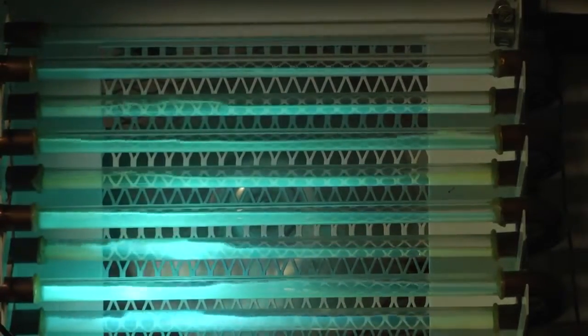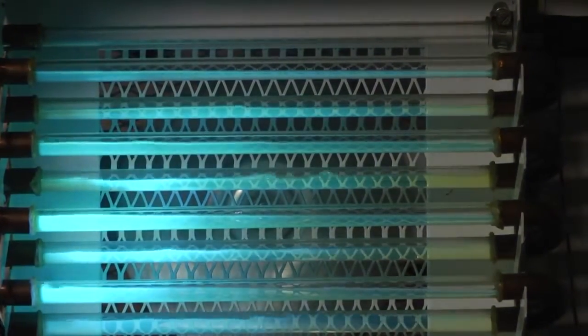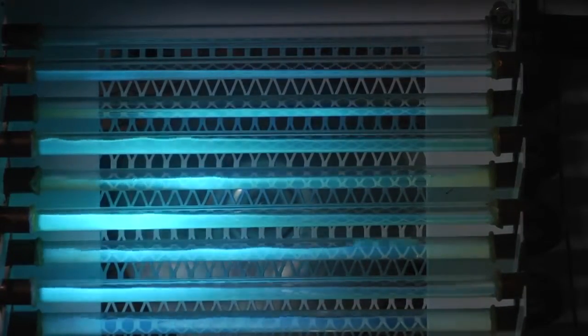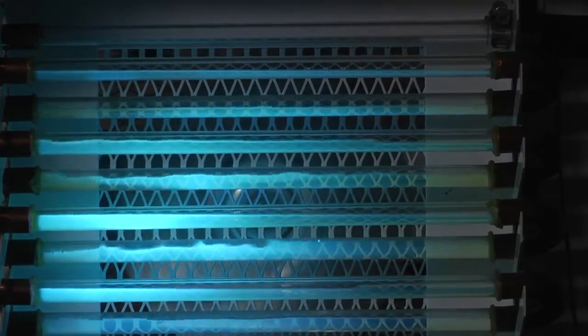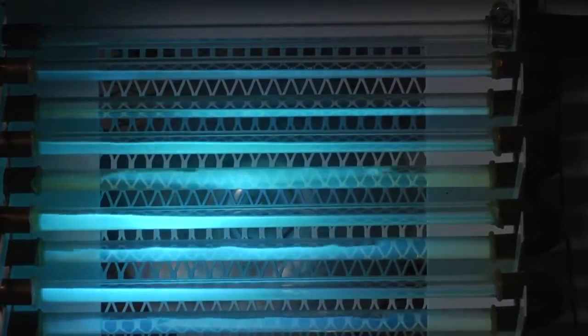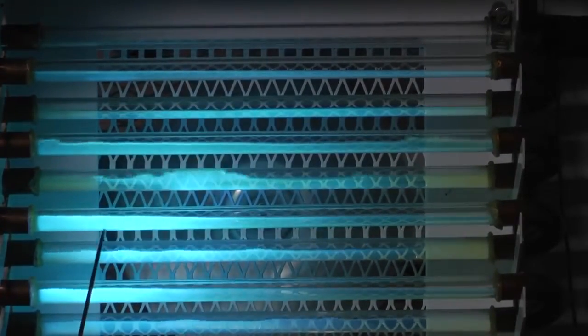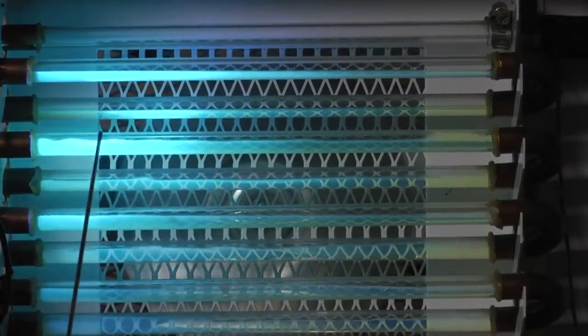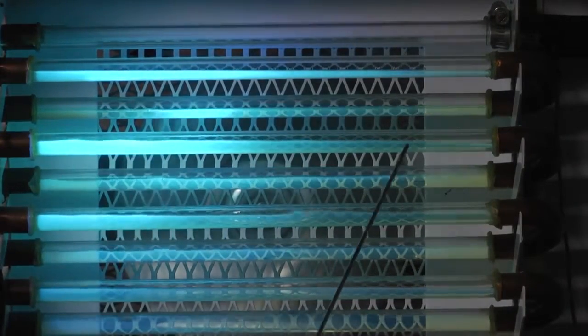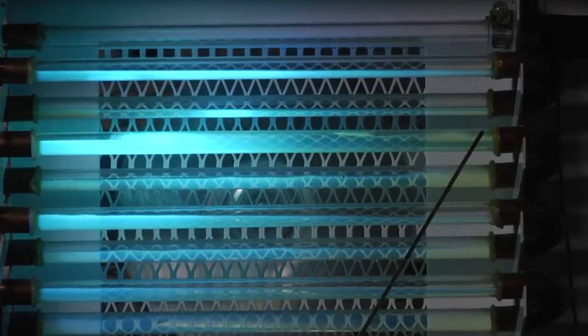As you look at our first tube here, you can see that about 20% of the refrigerant has transferred to vapor already. Now, the liquid refrigerant is going to continue to travel through our evaporator coil where the refrigerant is absorbing heat from the conditioned space. As it does, the heat that enters the refrigerant changes the state of the refrigerant. It continues to boil the refrigerant or evaporate it in the evaporator coil. You can see in the center here, there's less liquid and there's more vapor. As we go up to the top and we start off more liquid here, you can actually see a dramatic decrease in the amount of liquid at the last point of the tubing.